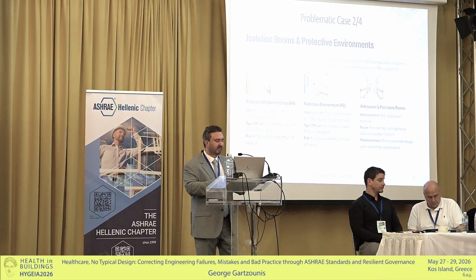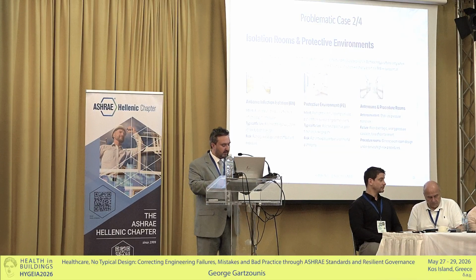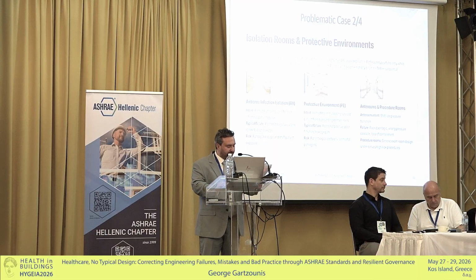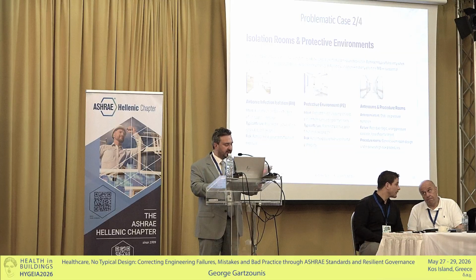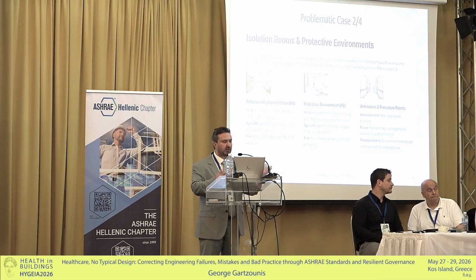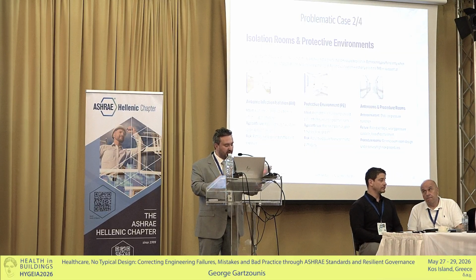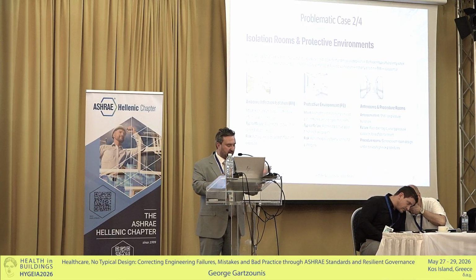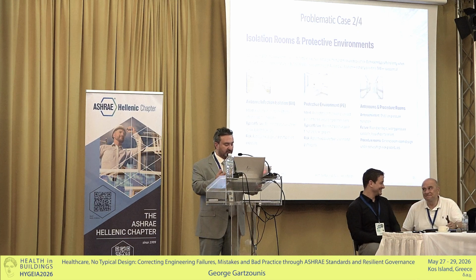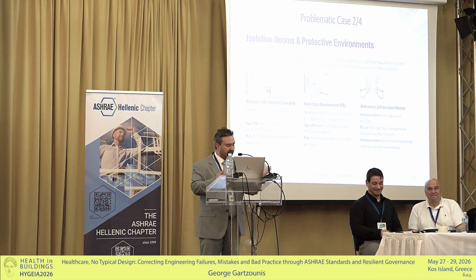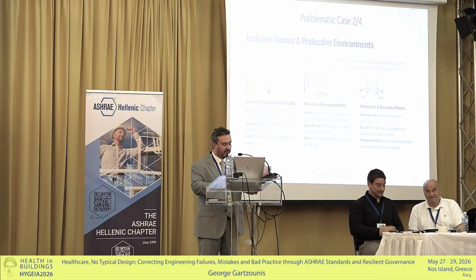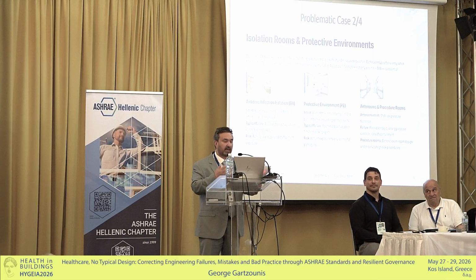Isolation rooms and protective environments are useful for explaining the difference between design intent and measured operation. A negative pressure room protects the outside environment from an infectious source. A positive pressure protective environment protects an immunocompromised patient from the surrounding environment. Both can fail if leakage, controls, door operation, and alarm response are not managed.